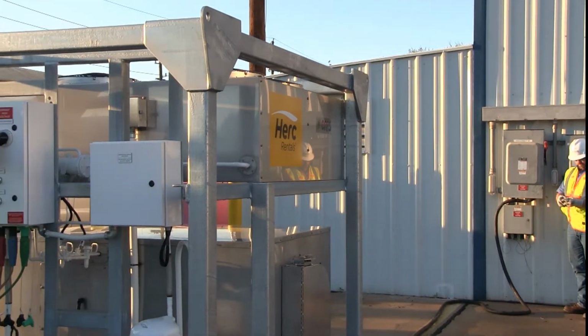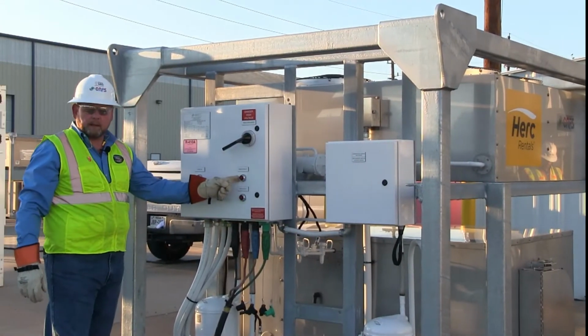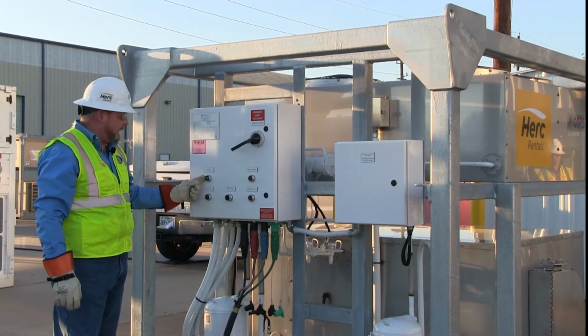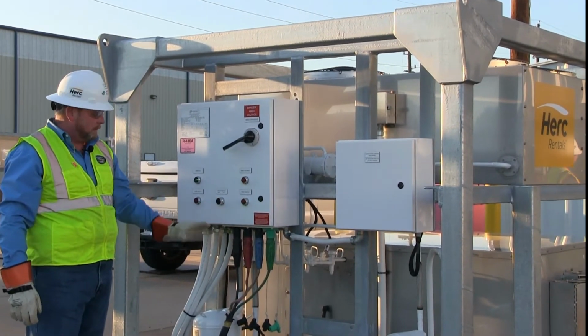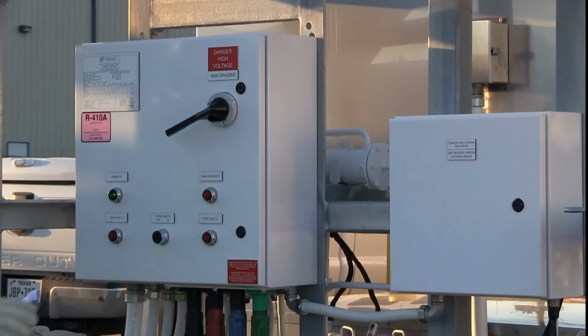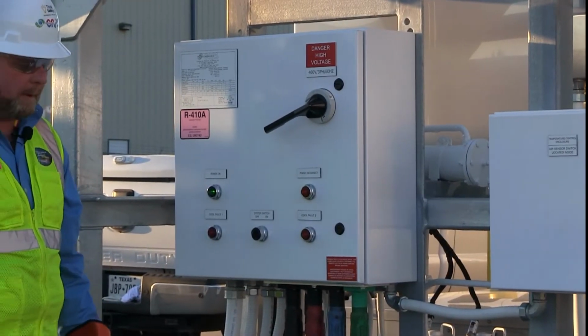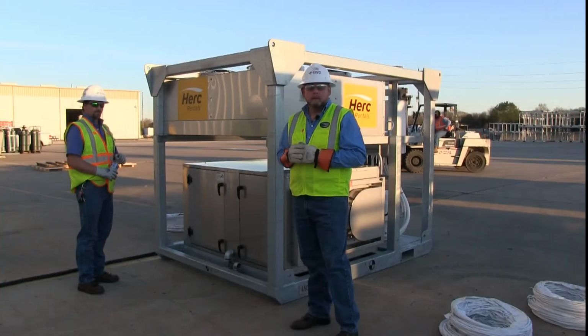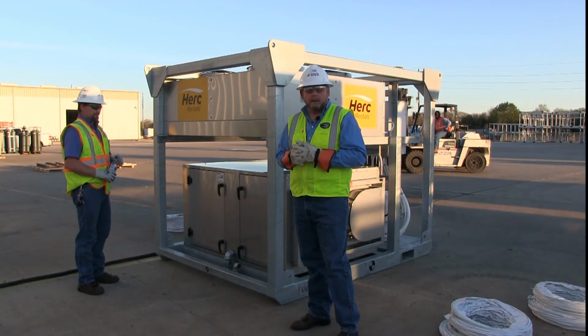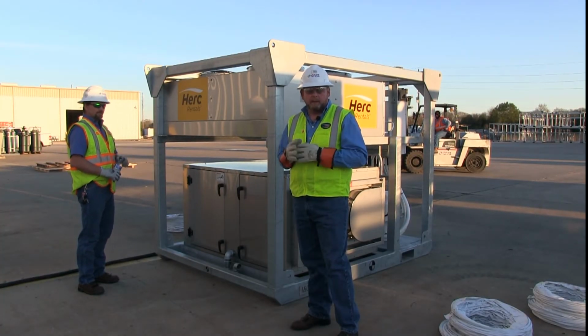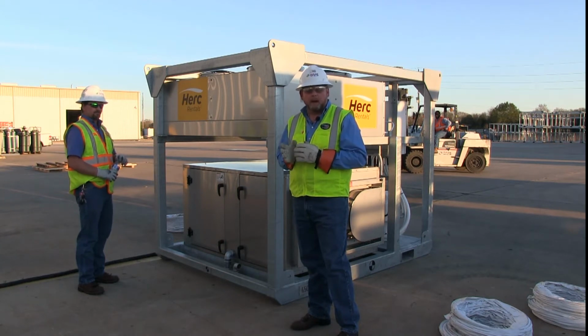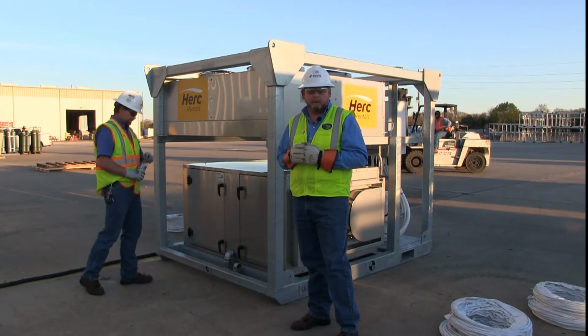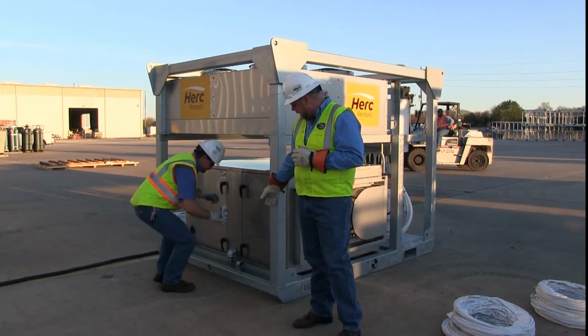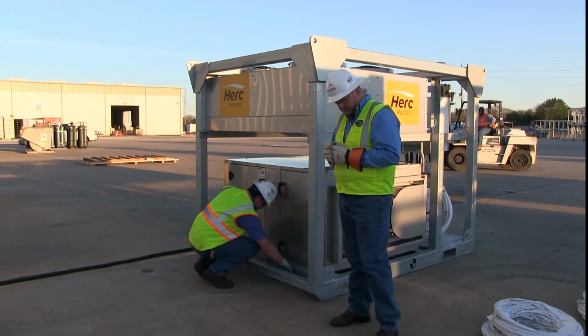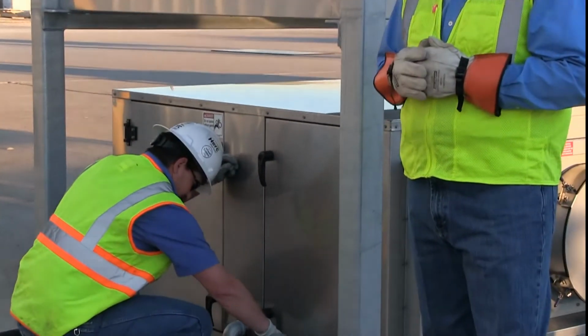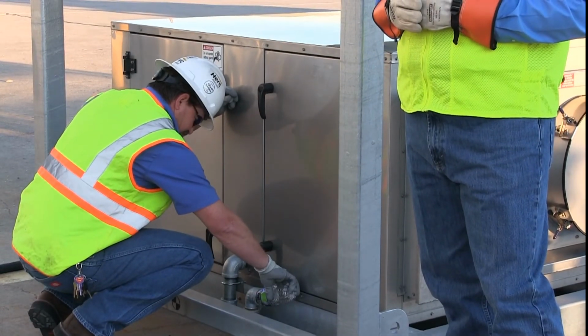Alright, power's on. Now the phase incorrect light is turned off. The power light is on. The system switch is off. The machine's now energized, and the compressors are currently warming up, being prepared to start. Now that our unit's been powered up and crankcase heaters are warming up, before we start the machine, we want to prime the condensate trap. We do that just simply with some water, and we'll demonstrate it here. Take a small bottle of water or a hose and just prime the P-trap so the unit properly drains.